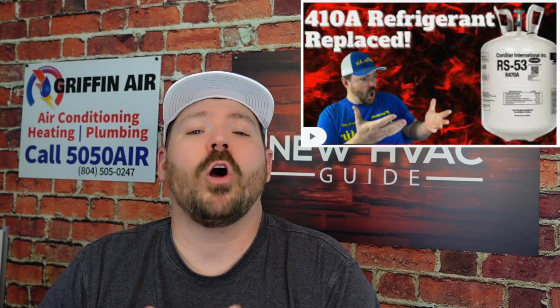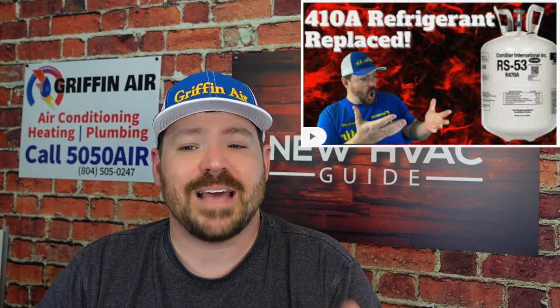So RS53, I believe, already exceeds that 750 GWP rating. I believe it's just under 1,000. So that tells you right there that this 410A refrigerant equipment, even the newest drop-ins for it, or at least the first one, is not going to pass with these standards here in California.